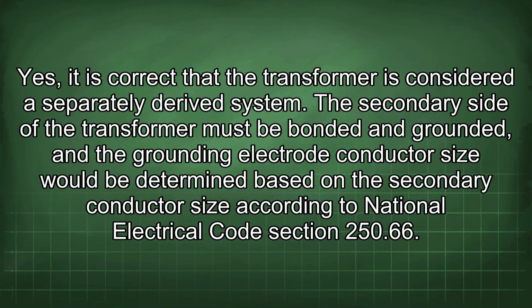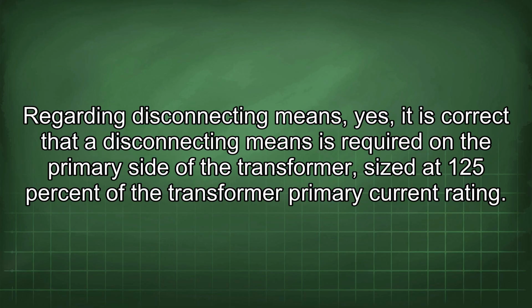Yes, it is correct that the transformer is considered a separately derived system. The secondary side of the transformer must be bonded and grounded, and the grounding electrode conductor size would be determined based on the secondary conductor size according to National Electrical Code Section 250.66. Regarding disconnecting means, yes, it is correct that a disconnecting means is required on the primary side of the transformer, sized at 125% of the transformer primary current rating.